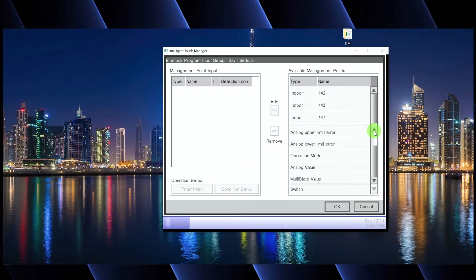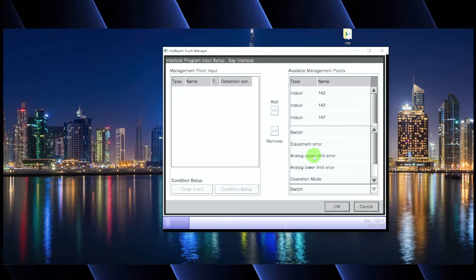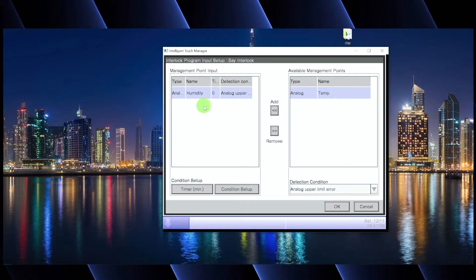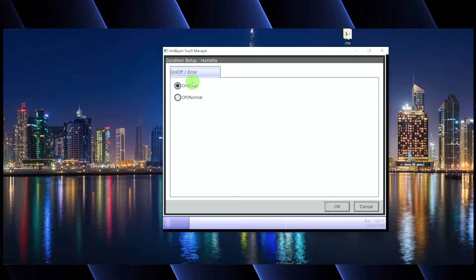As for the humidity sensor, when we programmed it we gave it a built-in alarm — if it gets above 70% humidity, it will automatically alarm according to the upper limit we programmed. So we're going to switch our input condition to analog upper limit, then grab our humidity sensor and move it over to the management point input section. We're saying: if the humidity sensor hits the upper limit we programmed into the management point, then we go down to condition setup and say that condition turns on.